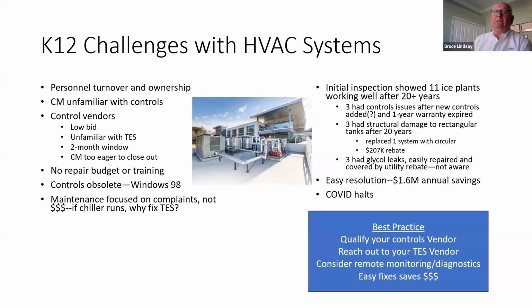3 of the schools that had rectangular tanks had structural damage. This is after 20 years, so they more than lasted a long enough time. But we decided to replace one school system with circular tanks, and we got a huge rebate from the utility. And then the third had glycol leaks, so we know we could figure out how to fix these things. So we called the manufacturer, had them come down and talk to us for a little bit. Lo and behold, simple solution is rip out the old tubing, put new tubing in, and the utility would pay for it. Great solution. We identified that we could save an additional $1.6 million a year by making these small little changes. Unfortunately, COVID came in and, well, things kind of went south.